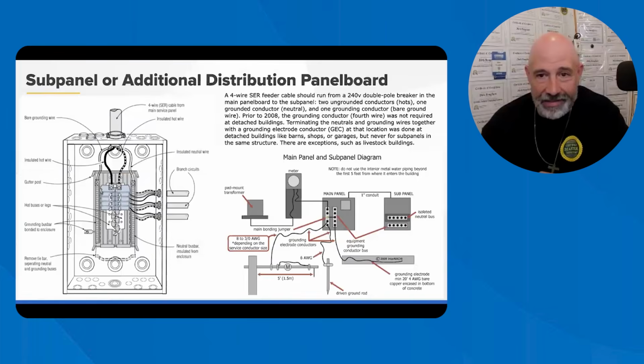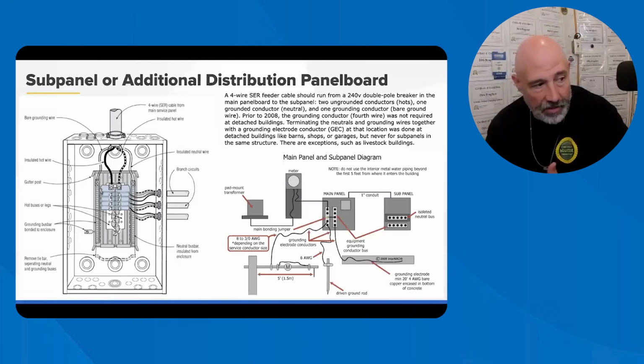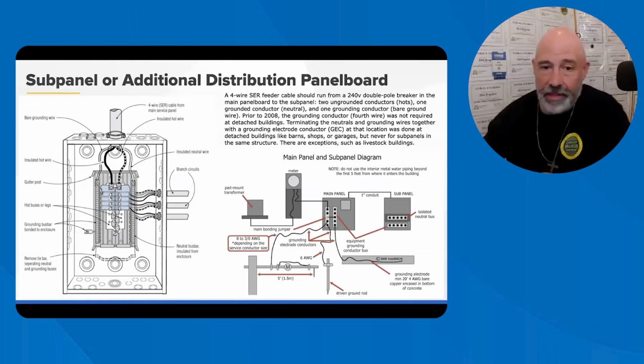And now here is the sub panel. You can see kind of the same thing, but in here we want the grounding bus bar to be bonded, but it should not be connected to the neutral wires. Well, got to get that out of my head.